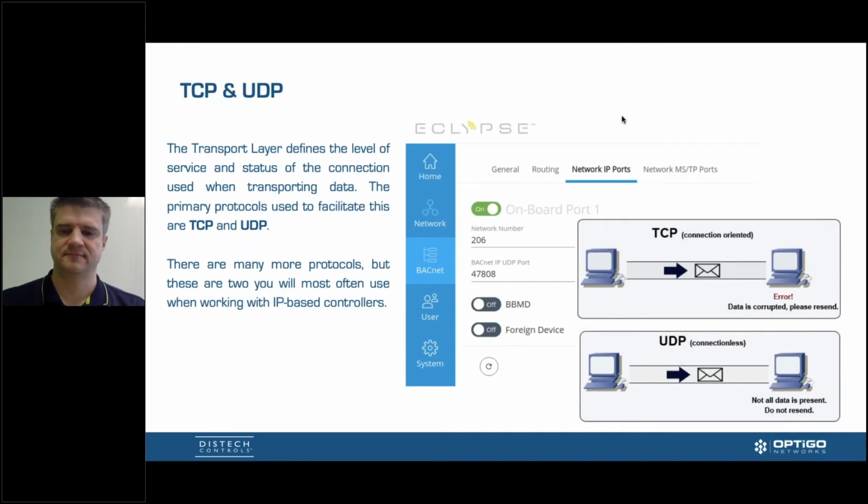In other layman terms, if you're streaming a video online, or streaming a video security camera, that would be a UDP kind of communication. It's connectionless. It doesn't care what you get or how many times you get it, or if you missed a small packet, you'll get the next packet later on. So in our world, it's something like an outside air temperature that we can do that broadcast, that global broadcast or that local broadcast.